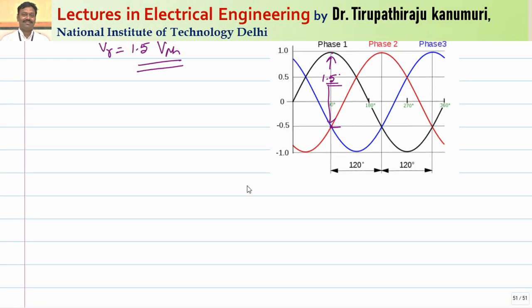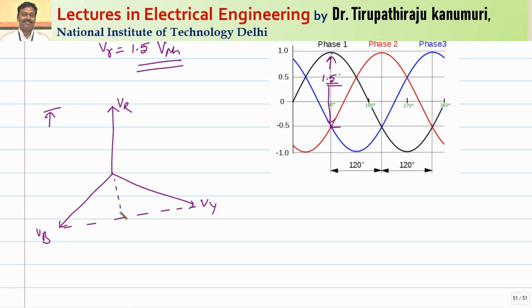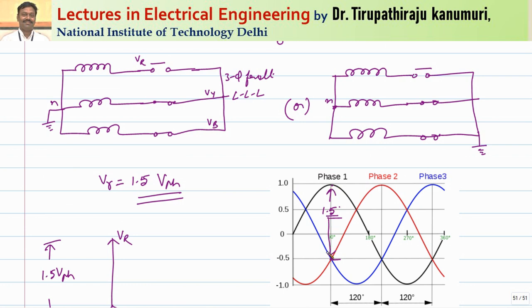To summarize: you have to take the instantaneous values, and the maximum instantaneous value gives you 1.5 times V_phase. Depending on the type of fault: if any fault — whether line-to-line, line-to-ground, or three-phase — is associated with ground, the maximum recovery voltage will be equal to the phase voltage only. If the fault is not associated with the ground (isolated neutral or ungrounded fault), the maximum voltage that can be reached will be equal to 1.5 times the phase voltage. This is the active recovery voltage.